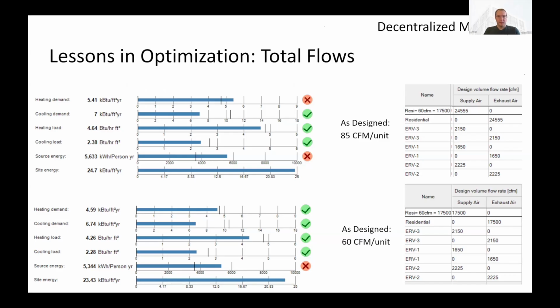All right, when we go back to the large decentralized multifamily, this was one of the genesis points for the whole presentation, and this is the last big example. The engineer originally designed this as a project with each unit having its own ERV with 85 CFM supply and exhaust. Typically these are one bathroom, one small kitchen sort of units. And they assumed they would not just use 20 CFM exhaust, which is the required amount for the bathroom, but give themselves some leeway up to 25 CFM.